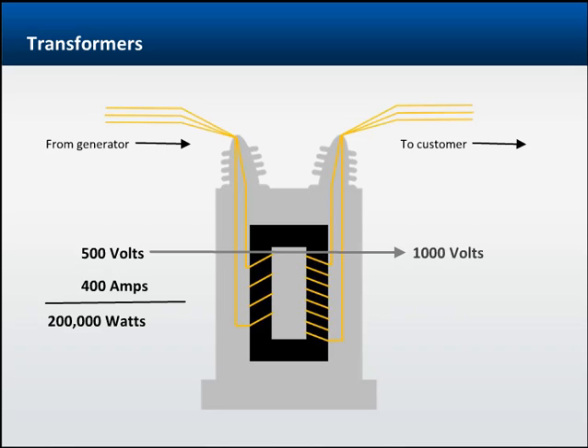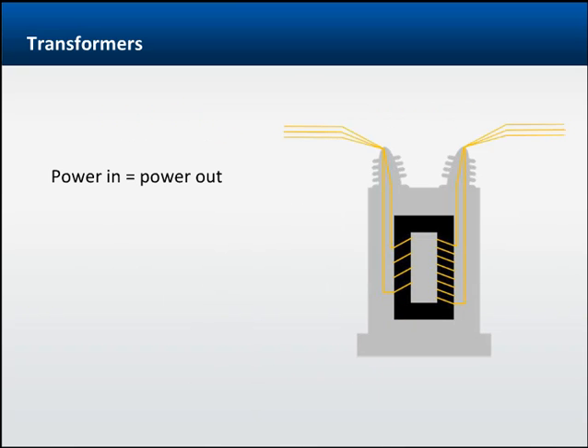Since the transformer is increasing the voltage to 1,000 volts and the power remains the same, the amps will be reduced to 200. In general terms, the power into a transformer equals the power out. But this is not exactly true, since there is typically a small loss of power due to the inefficiency of the transformer, which might equal two to three percent.